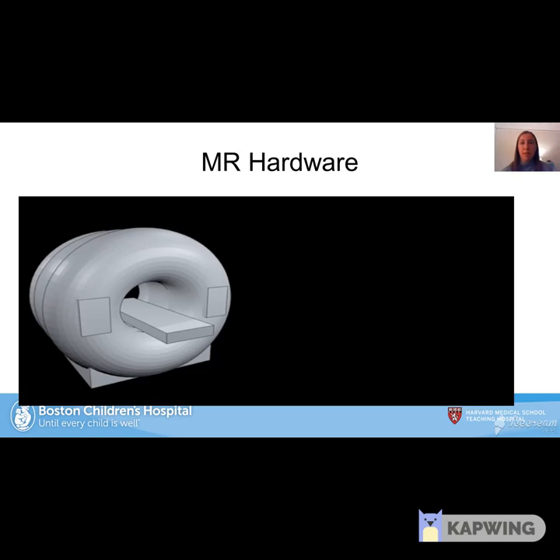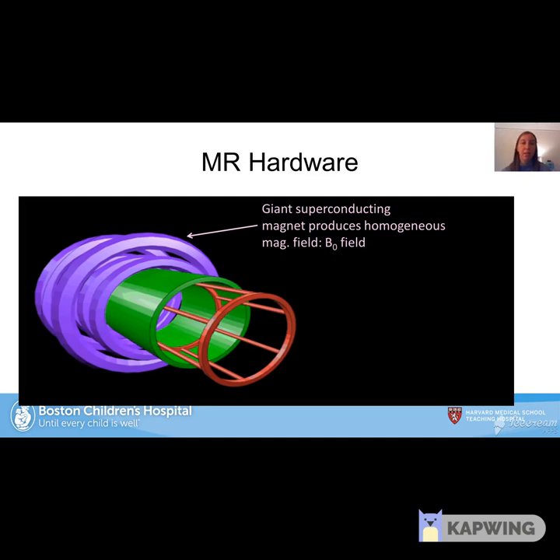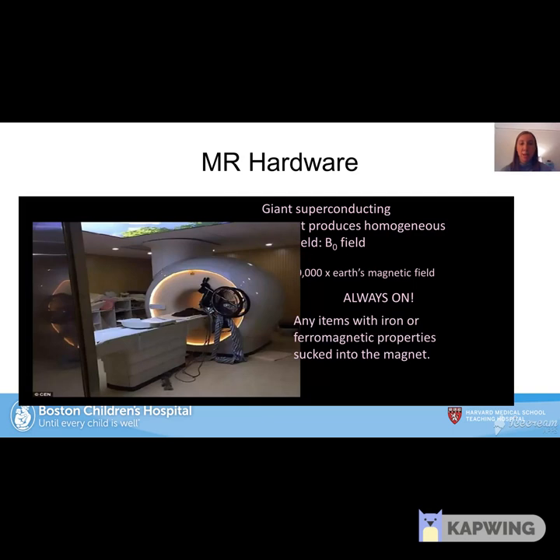Before getting into MR imaging, let's go over some of the hardware used. An MR machine has three main internal components. The first is a giant superconducting magnet that produces a homogeneous magnetic field — the B-naught field — about 10,000 times stronger than the Earth's magnetic field. This magnet is always on, weekends, holidays, every day. Once the MR machine is commissioned, it operates at that field strength for its entire lifetime. Walking in with a cell phone, credit cards, or anything ferromagnetic could cause them to be sucked into the magnet or wiped.